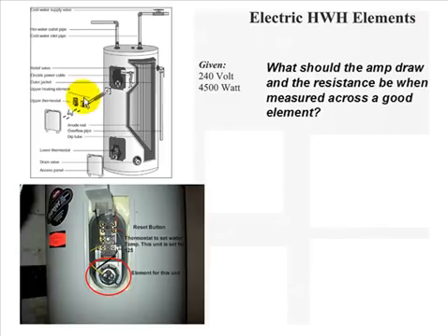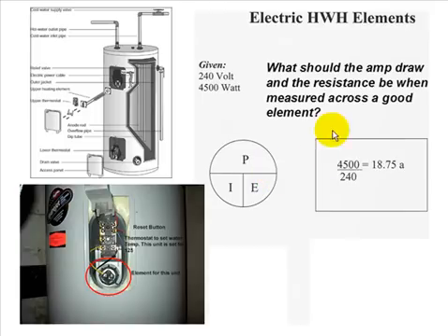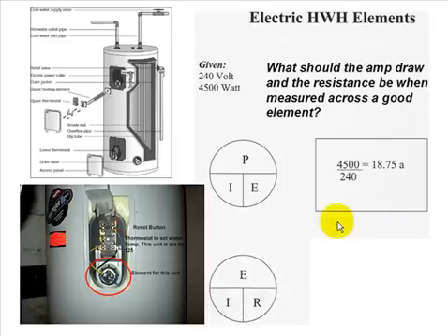What should the amp draw and the resistance be when measured across a good element? A good element. What should it show up as? Well, P over IE. We're going to solve for power. We know that it's 4,500 watts over 240 volts. So watts divided by volts is going to give me 18.75 amps. So if this heater is good and I hook up my amp probe to the element, you know, split the wires, hook up my amp probe to one of the elements, that's exactly what I should read. Or something very close to that. Your meter is going to do a little rounding, but that's about all.